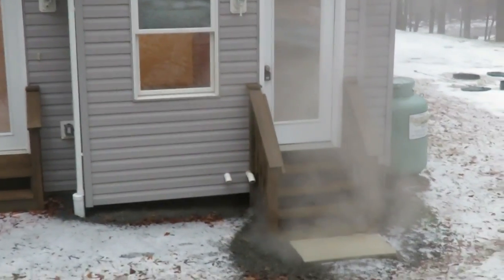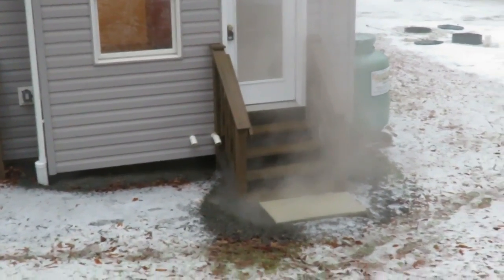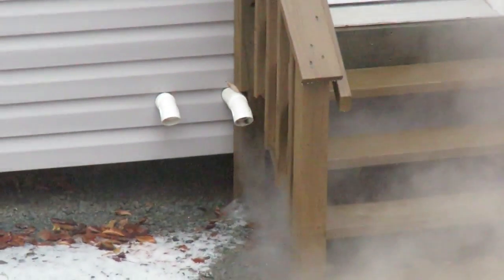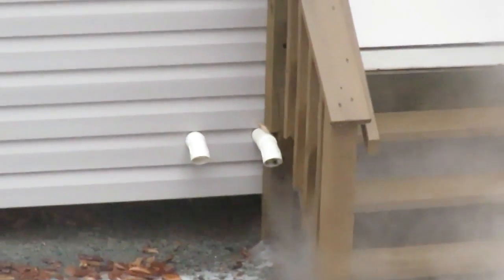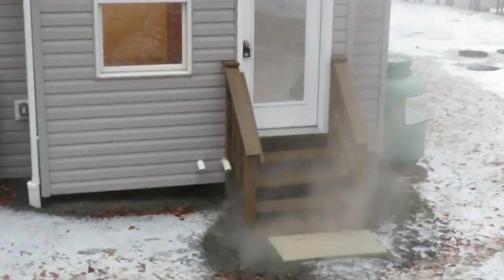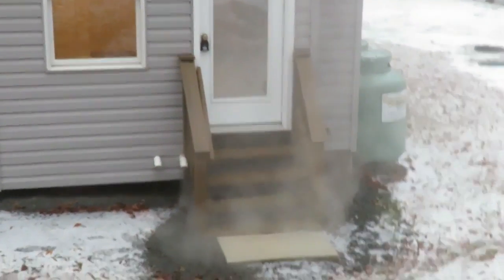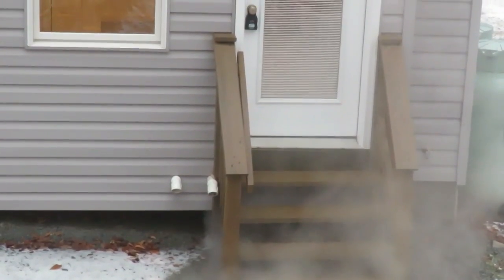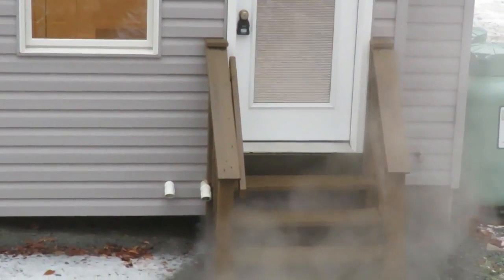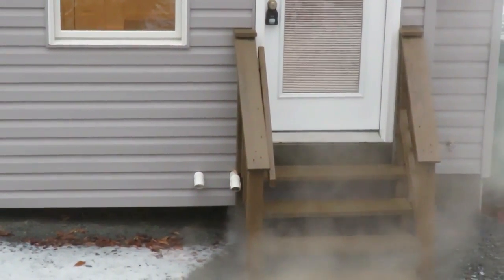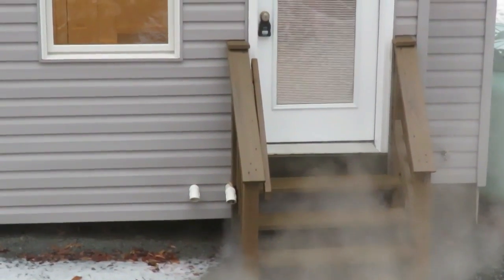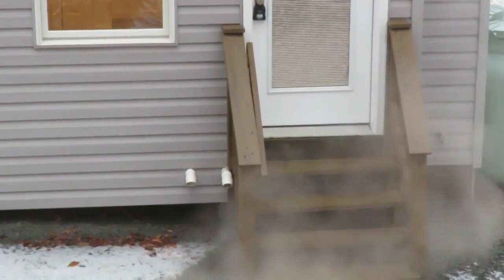Here we are outside looking at the exhaust system, and what we see here is that the exhaust pipe and the intake pipe are close together. In addition, they are not far enough from that door. So you can see the exhaust coming out, and that will penetrate right under that door or even into that window. So we are going to have someone take a look at that as well.